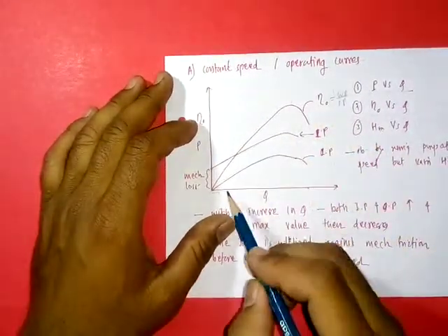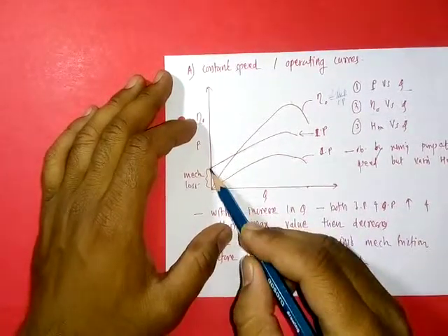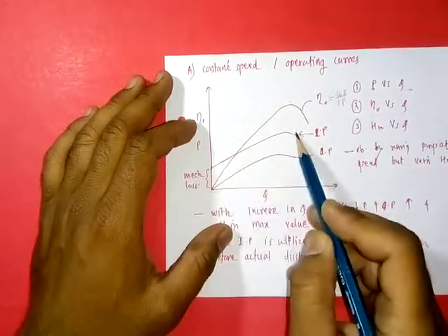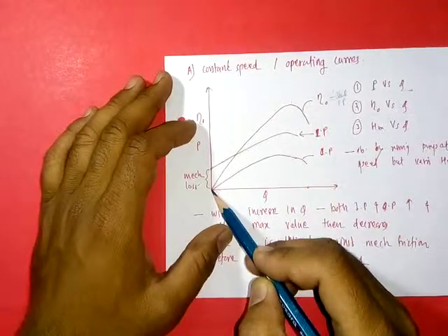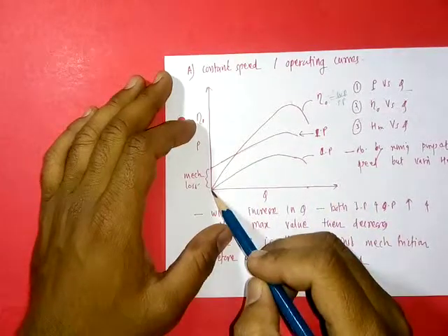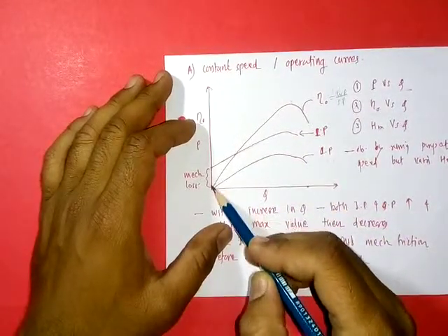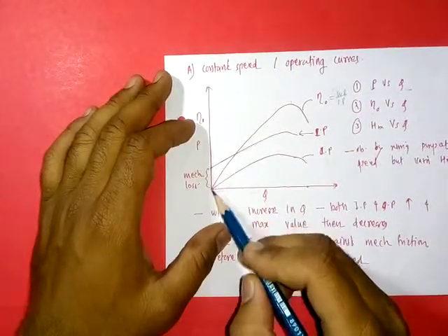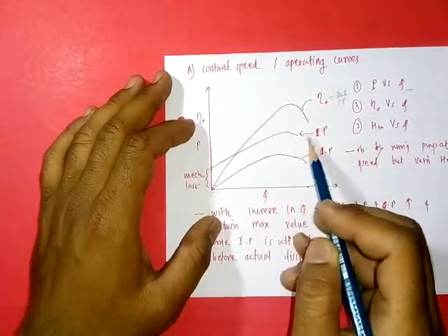As discharge increases, power increases, attends a maximum value, and then decreases again. Overall efficiency also starts from the origin, attends a maximum value, and then decreases. But input power does not start from the origin — it starts from some nonzero positive value even when discharge is zero.